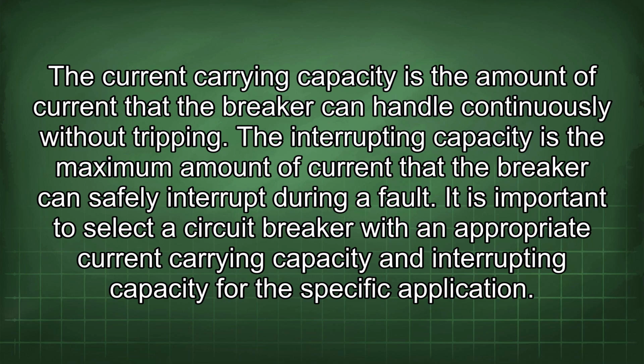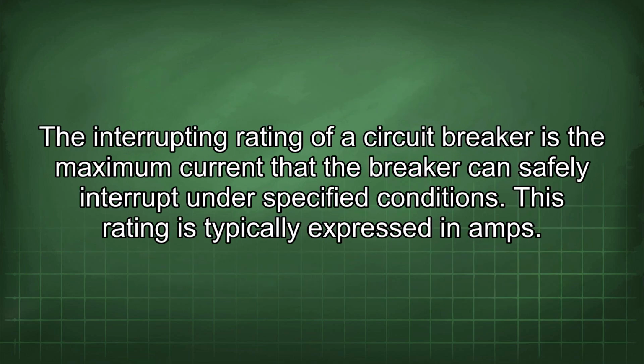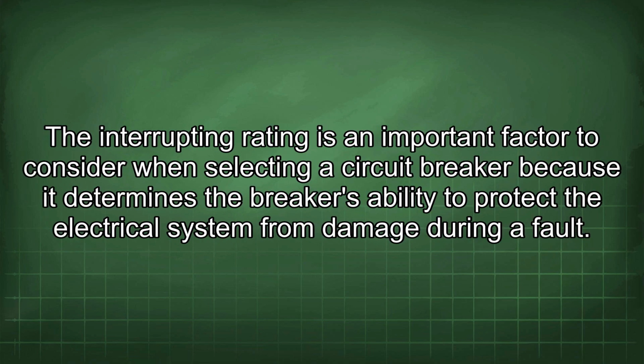It is important to select a circuit breaker with an appropriate current carrying capacity and interrupting capacity for the specific application. The interrupting rating of a circuit breaker is the maximum current that the breaker can safely interrupt under specified conditions. This rating is typically expressed in amps. The interrupting rating is an important factor to consider when selecting a circuit breaker because it determines the breaker's ability to protect the electrical system from damage during a fault.